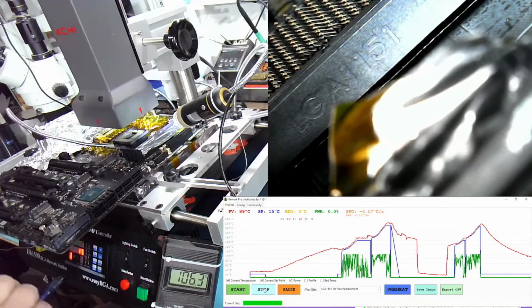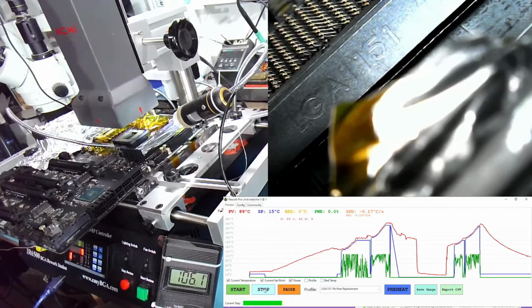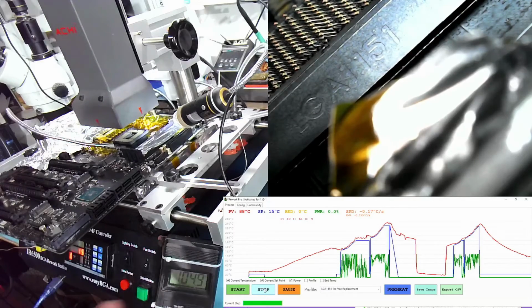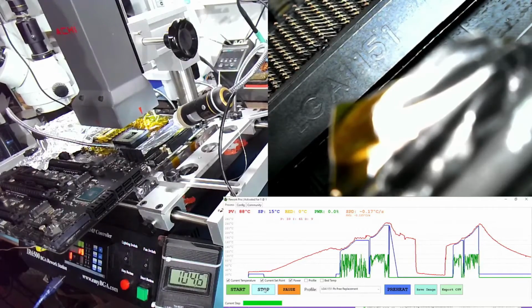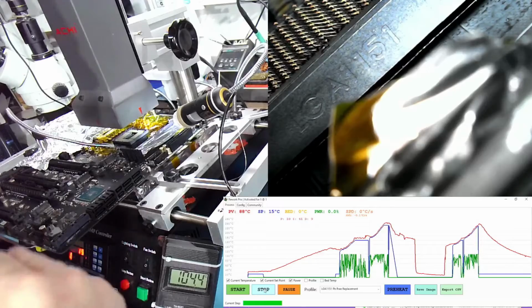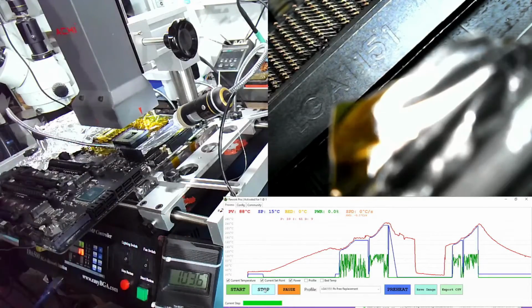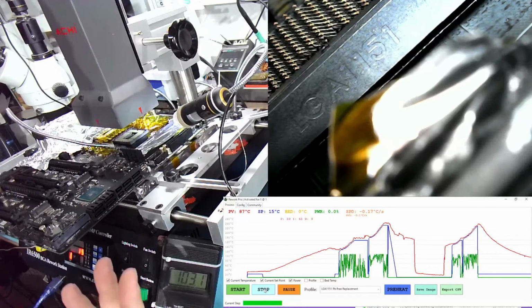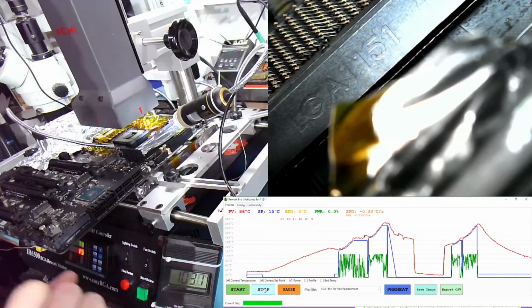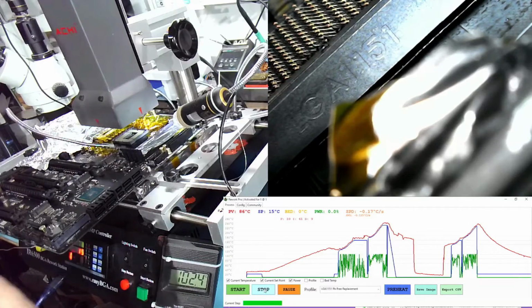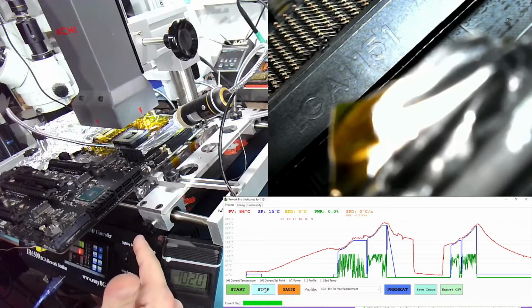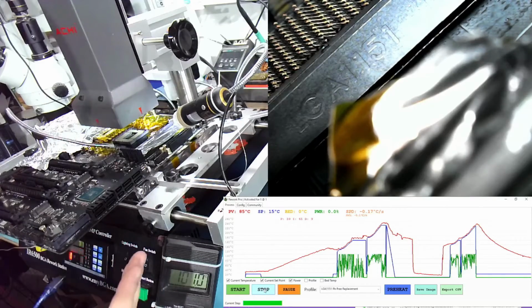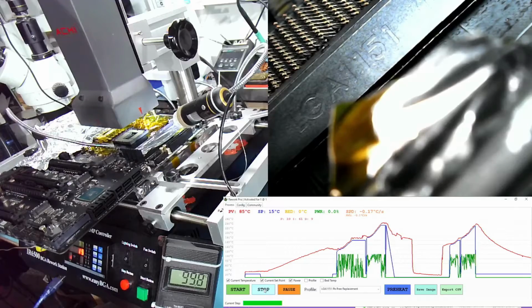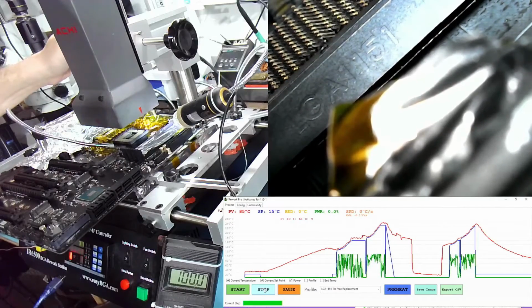Here's the mistake I made. When I introduced the thermocouple calibration, I only applied it to the reading temperature. So on the graph you can see this major overshoot. The set point is way lower than the temperature, because the temperature the software reads is increased by that calibration factor. But when we send the set point to the machine, it should be lowered by that amount, and I forgot about that, or didn't even think about it. So we were setting the temperature too high.